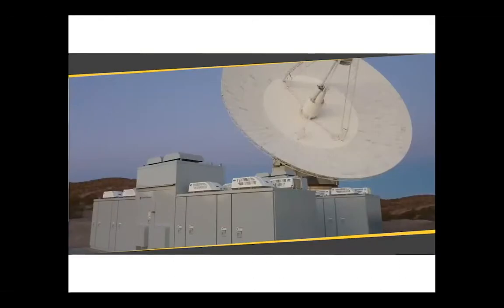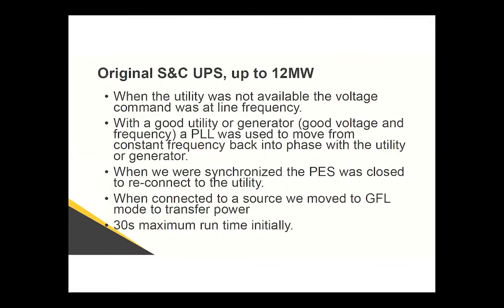Here's a picture of a 4 megawatt, 5 MVA system at a NASA Deep Communication Space System. Each of the little RV air conditioners is one inverter battery set. Those are used to keep the batteries at the right temperature so that we can warrant that system. Whenever we went into the UPS mode, we just run at a constant frequency. And we do that for a while.